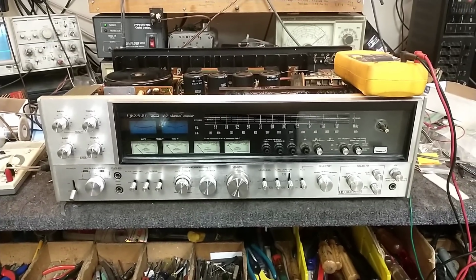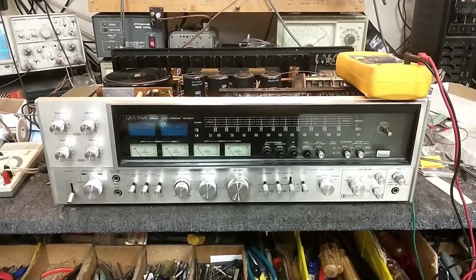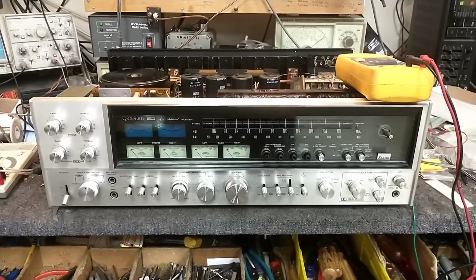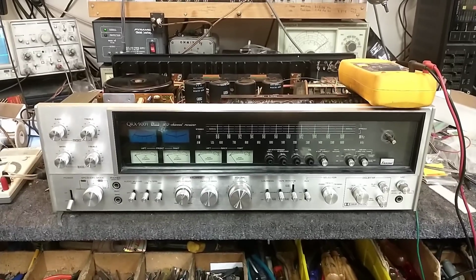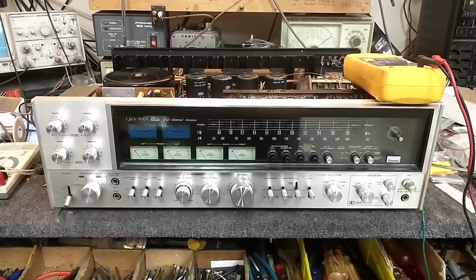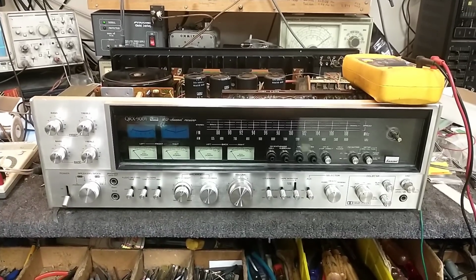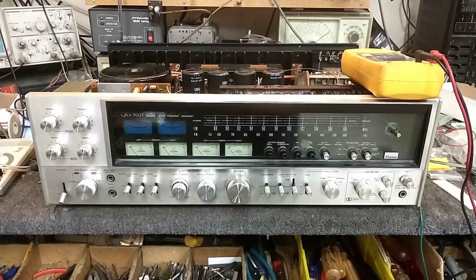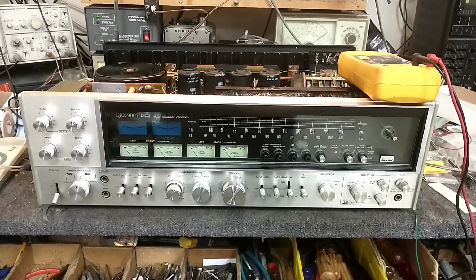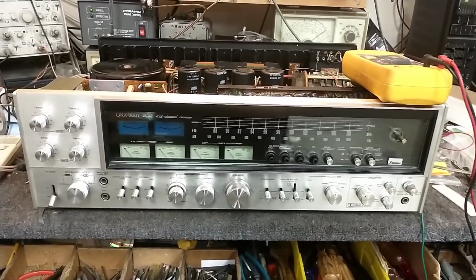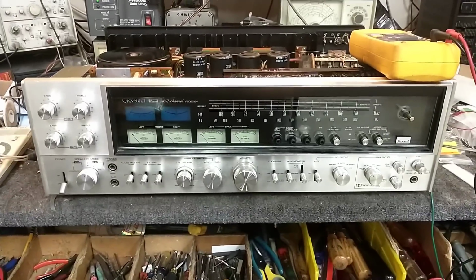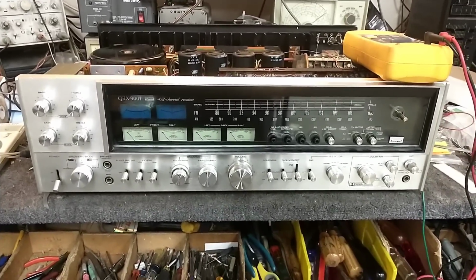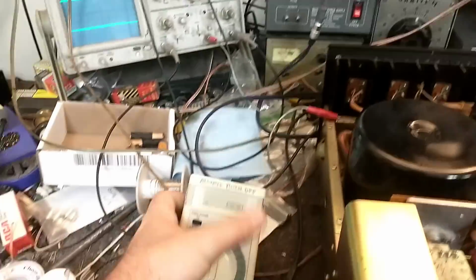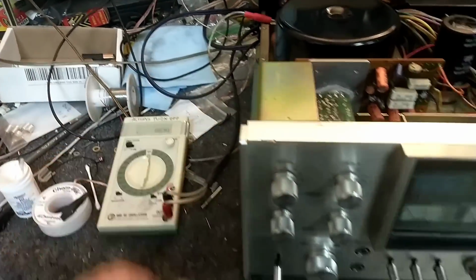Okay, so now we're going to go through the decoder calibration. Now, what you really need are two separate signal generators, and if they're a grounded instrument, you need to lift the grounds on them. Otherwise, when you tie them together to the receiver, you're going to get some cancellation, and at least one or more channels will get shorted to chassis. So they need to float from ground. So what I have is nominally an app on my phone that does it all through a stereo cable. But if you don't have that, or you want to demonstrate it, I have a main signal generator up here, and then I have a handheld which I have wired out of phase, which you will need to do.